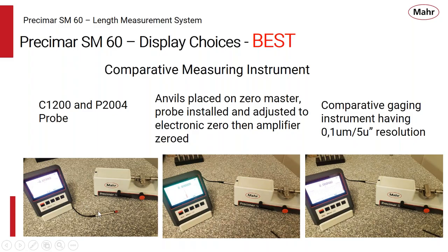case we're going to use this as a comparative measuring system. So what you can see here, I have a master disc in place. We're going to put the probe in place, bring that to electronic 0, lock it into place, zero out the amplifier, and now we can put our parts in there and make comparative readings to our master to 5 millionths of an inch resolution. So from great to better to best, we have lots of options to make this a high performance length measuring machine.